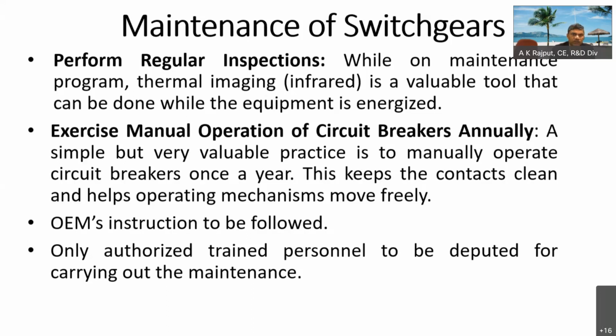And then manual operation should be tried whenever the opportunity arises. If a fault has taken place and there is an opportunity, the breaker should be taken to the service position if it is trolley mounted, and not the service position but the test position, and in the test position it should be tried manually. And when long shutdown opportunities are there, each and every operation and each and every part should be checked, whether it is moving freely or not, whether it is stuck somewhere, whether it is making noise, or if there is some mechanism or link, whether the link is weak.